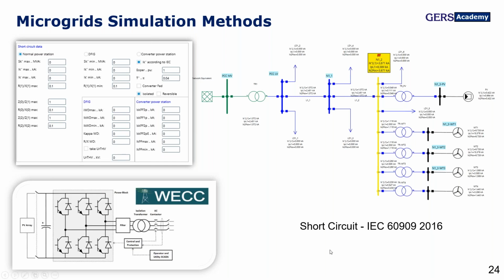Another standard is the new IEC 60909, the latest standard that considers the penetration of this kind of sources, where some of them in general can be considered as current sources. It means that if we have different fault locations, the contribution of this kind of source will be the same. This is the model that we can set for this kind of source: normal power station, DFIG station, or the typical application in the PV system in converter applications.